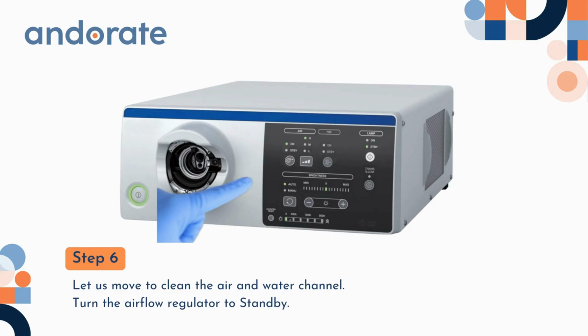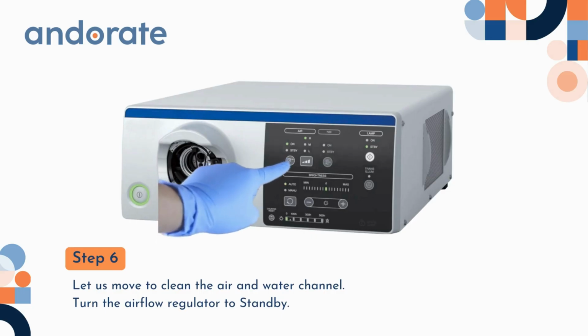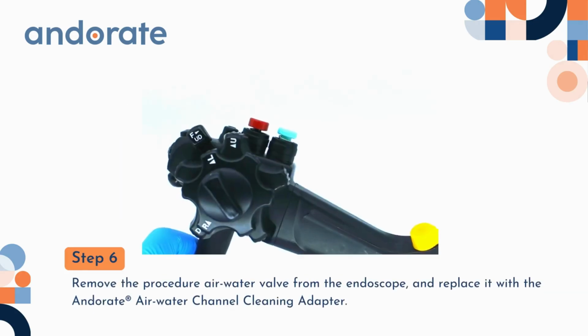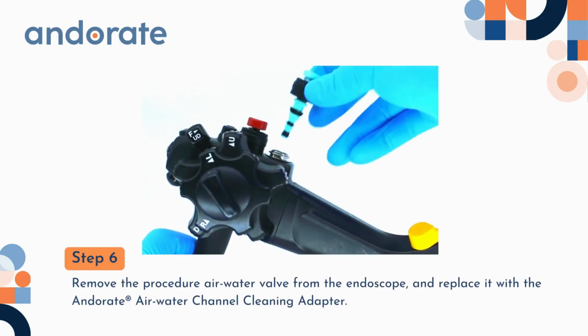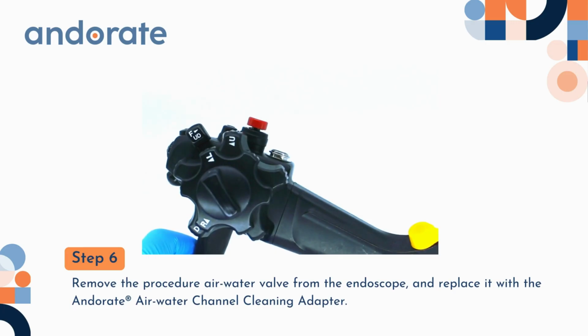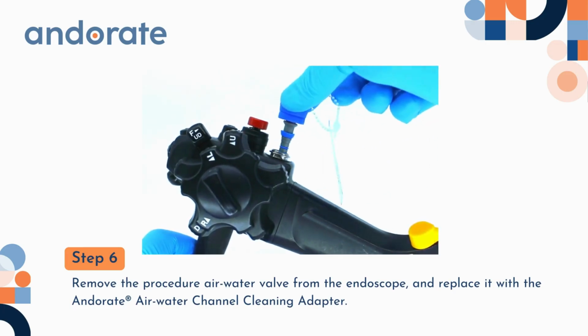Step 6. Let's move to clean the air and water channel. Turn the airflow regulator to standby. Remove the procedure air-water valve from the endoscope and replace it with the Andorate air-water channel cleaning adapter.